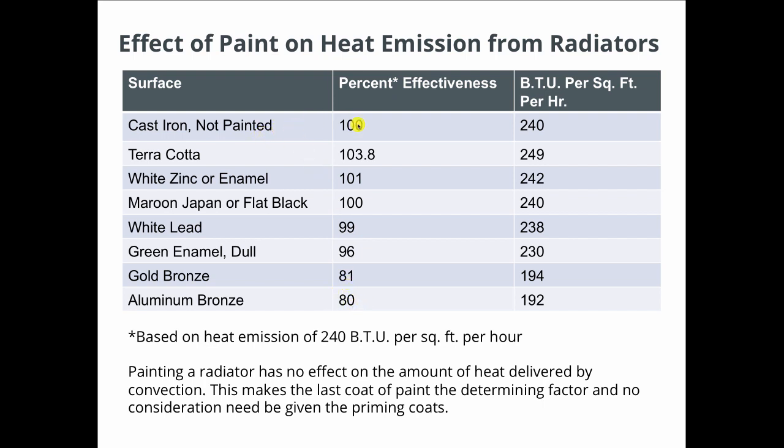So a radiator that's bare, not painted at all, puts out 240 BTUs per hour. If you paint it with this aluminum bronze paint, the output drops to 192 BTUs per hour. And it's only the last coat that matters.